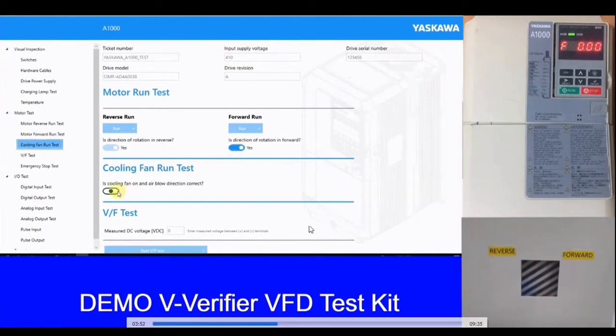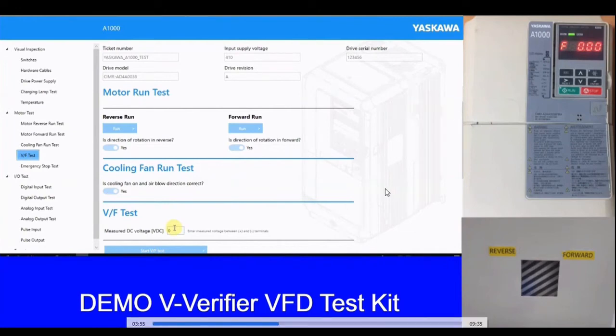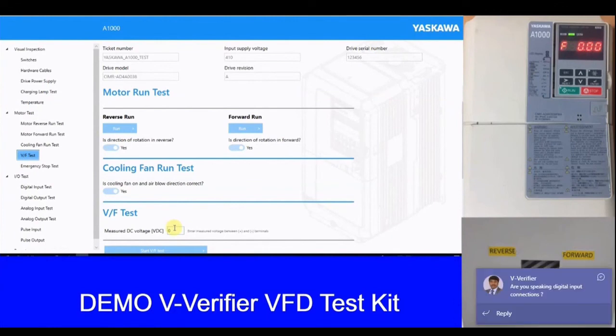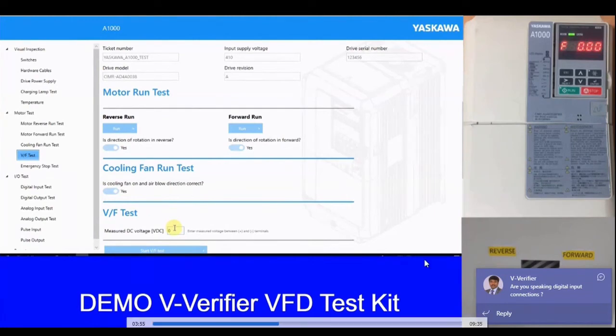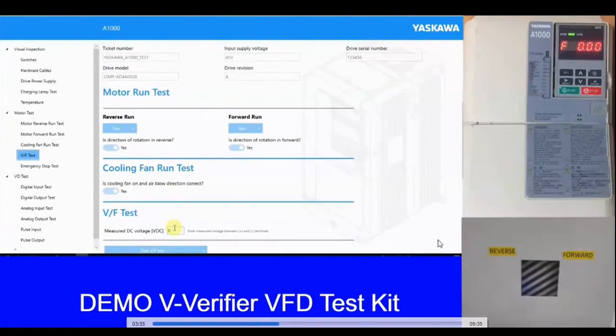Next we have the cooling fan test. If the VFD doesn't have a cooling fan — for smaller ratings like 4 ampere or 2 ampere VFDs — this test will not be displayed. Based on what model you enter, the tests are decided. If you enter the wrong model number, the V-Verifier will detect that the connected VFD and the selected testing VFD are mismatching, and it will not allow you to proceed. The V-Verifier has a verification point where it reads data from inside the VFD and matches the details — wrong entry creates a mismatch and blocks the user from proceeding.